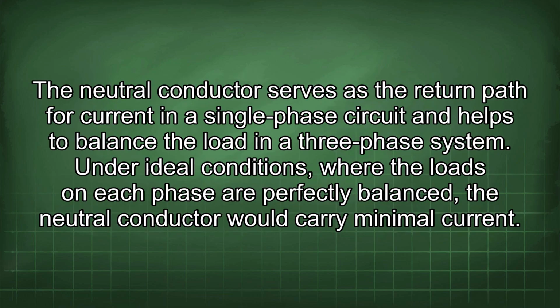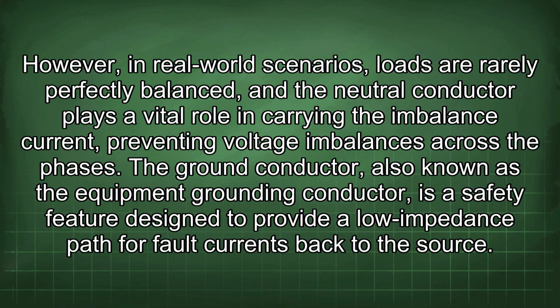The neutral conductor serves as the return path for current in a single-phase circuit and helps to balance the load in a three-phase system. Under ideal conditions, where the loads on each phase are perfectly balanced, the neutral conductor would carry minimal current. However, in real-world scenarios, loads are rarely perfectly balanced, and the neutral conductor plays a vital role in carrying the imbalanced current, preventing voltage imbalances across the phases.